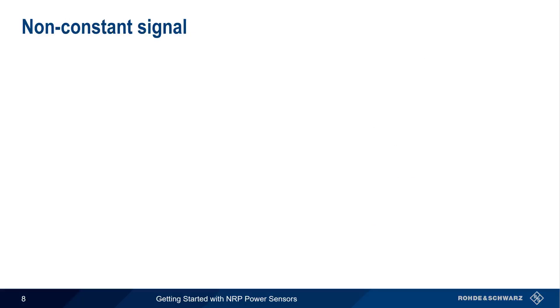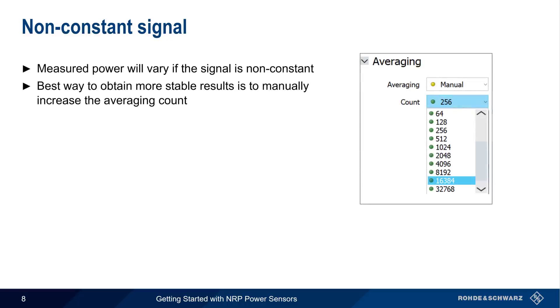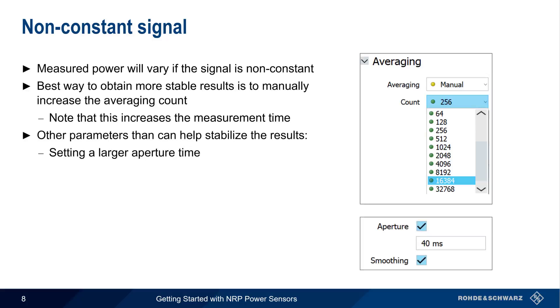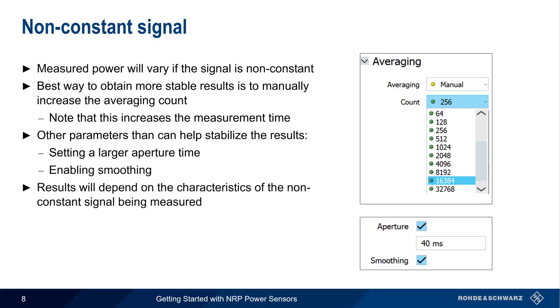If we have a non-constant signal, the displayed power will fluctuate over time. The best way to deal with this is to manually increase the average count, which should lead to more consistent measurement results but will also increase the measurement time, sometimes dramatically. Other ways of stabilizing the measurement results include manually increasing the aperture time and/or enabling smoothing. How much of an effect these have will, of course, depend on the nature of the non-constant signal being measured.